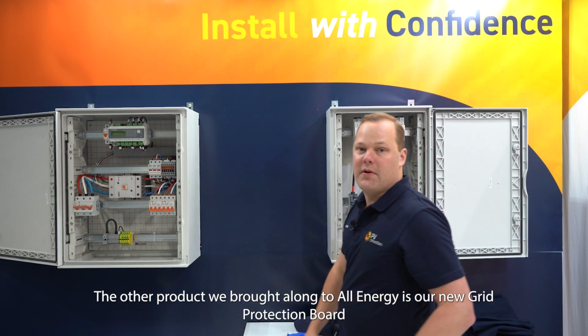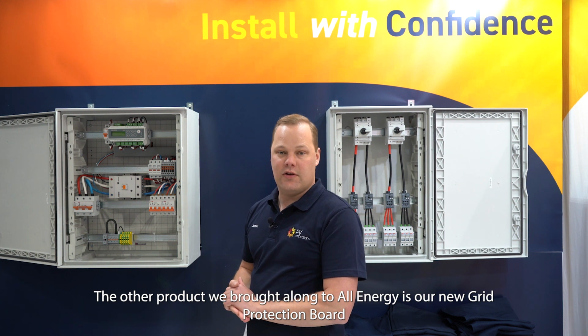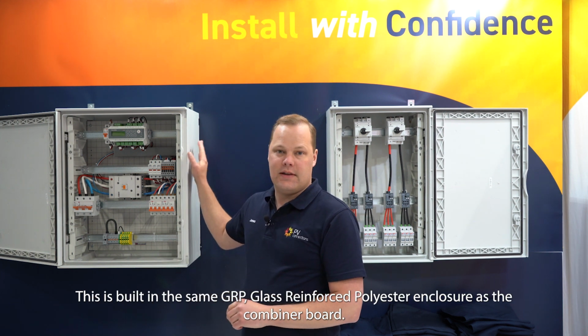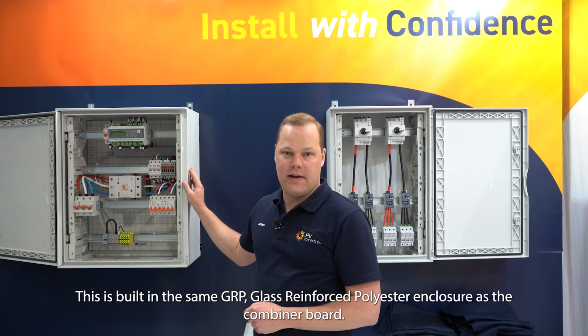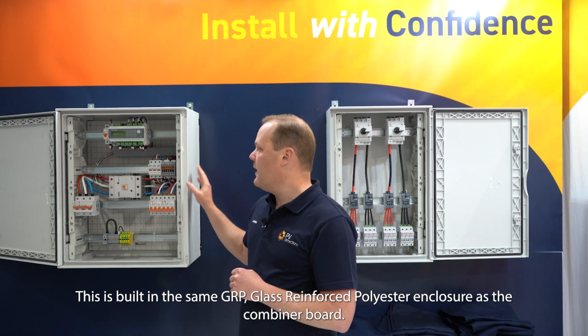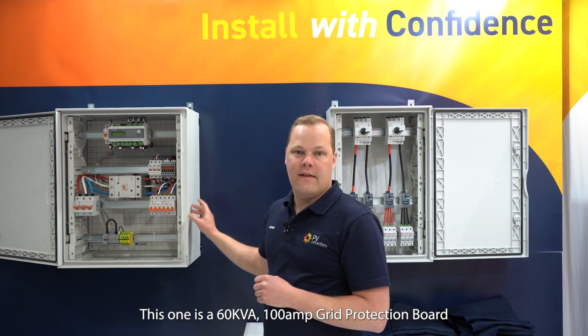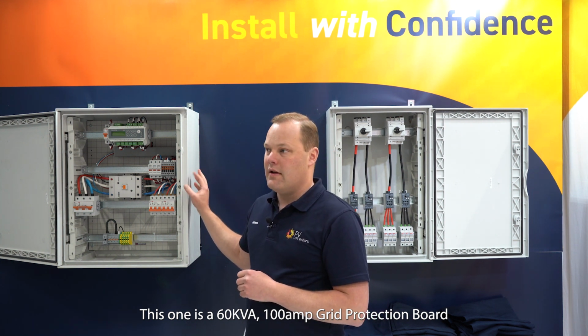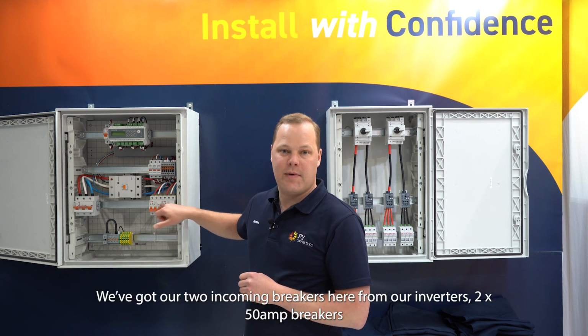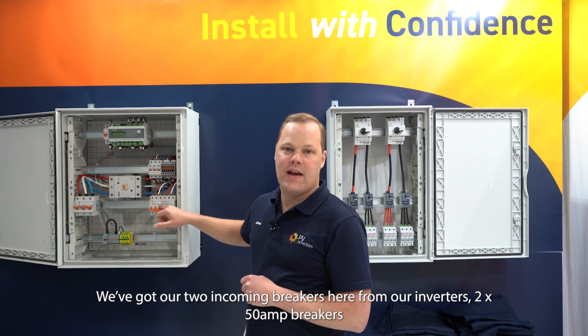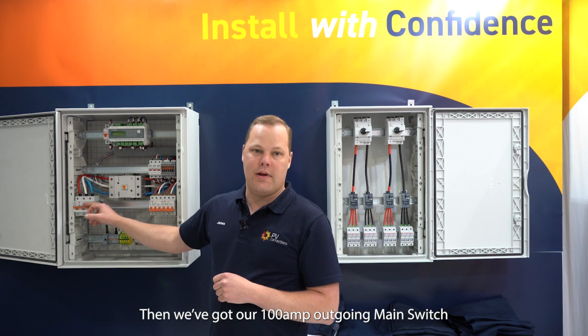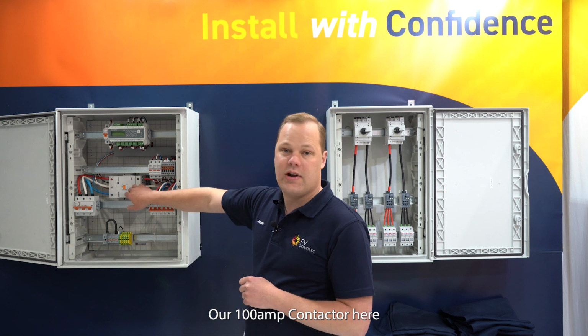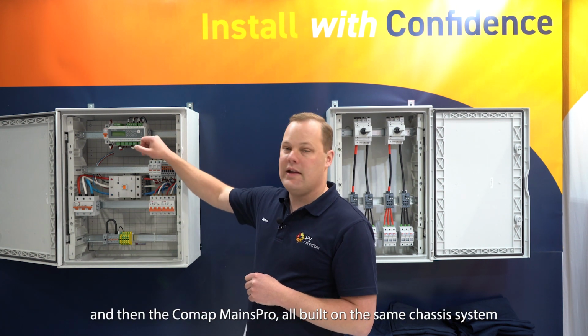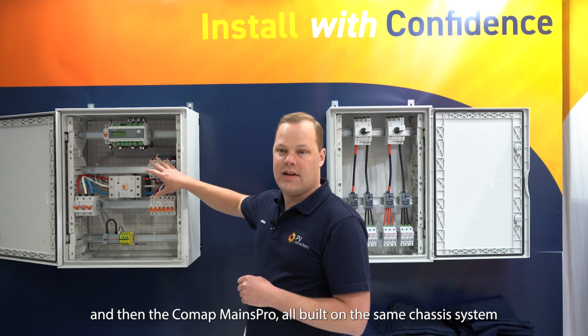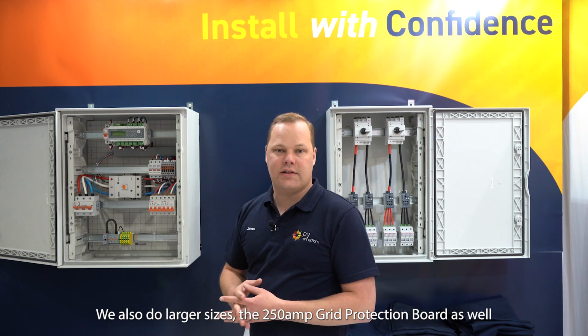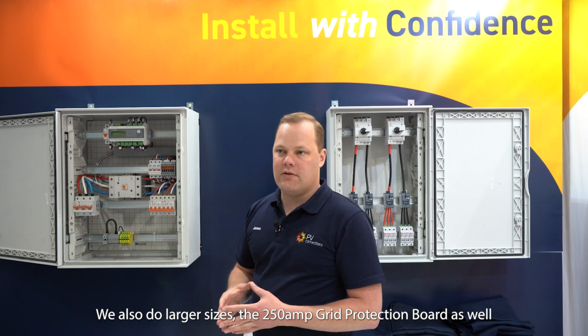The other product we brought along to All Energy was our new grid protection board. This is built in the same GRP glass reinforced polyester enclosure as the combiner board. This one is a 60 kVA, 100 amp grid protection board. We've got our two incoming breakers here from our inverters, 2 x 50 amp breakers, then our 100 amp outgoing main switch. We've got our 100 amp contactor here, and the ComAp MainsPro, all built on the same chassis system. We also do the larger sizes, the 250 amp grid protection boards as well.